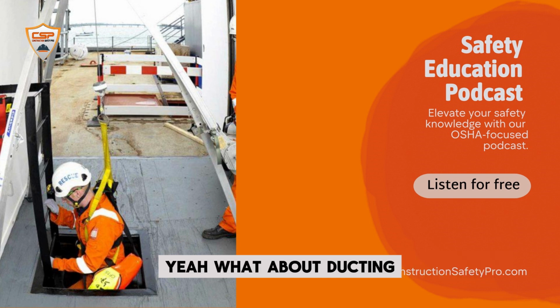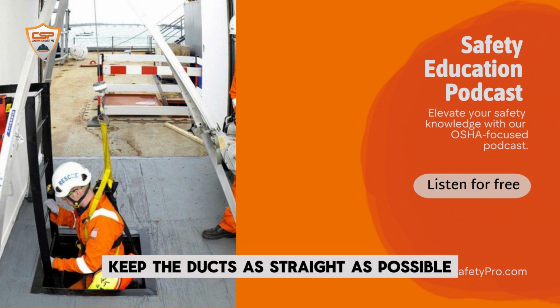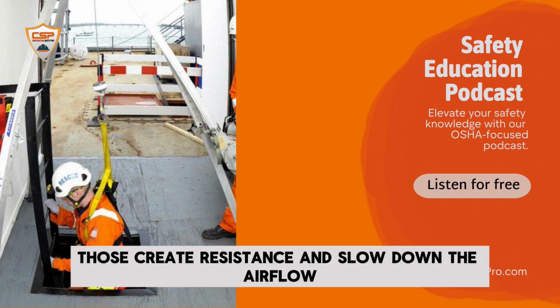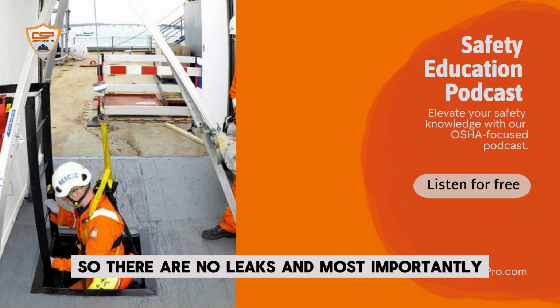Yeah, what about ducting? Well, you need to use the right size duct so you don't restrict airflow and make the fan work harder. Keep the ducts as straight as possible and avoid any sharp bends or kinks. Those create resistance and slow down the airflow. Make sure all the connections are tight so there are no leaks.